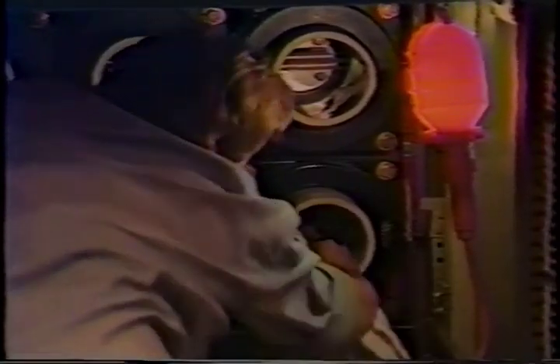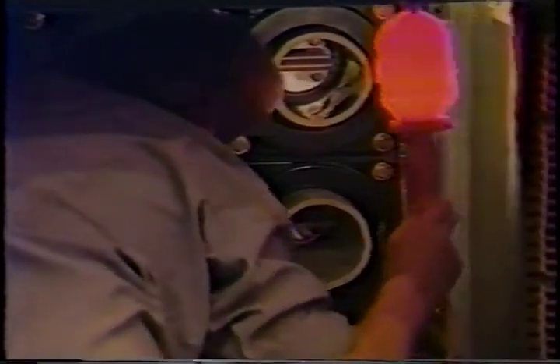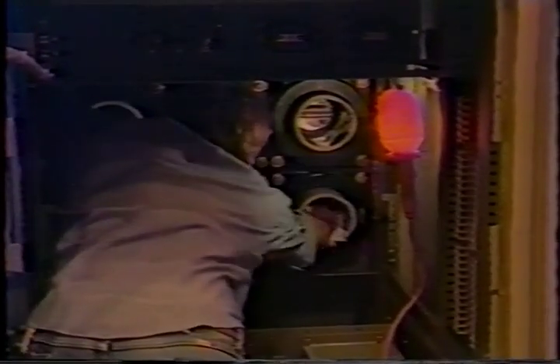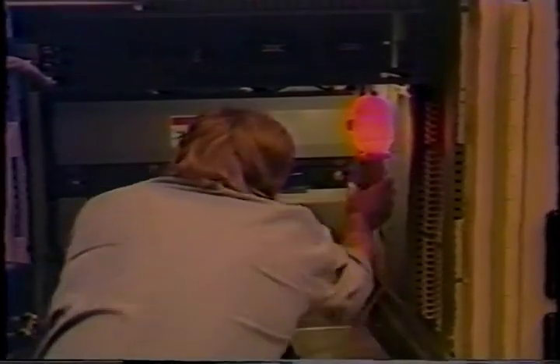For maintenance of disconnecting contacts and supports, remove each breaker from its compartment. De-energize primary circuits and expose primary contacts and their supports. Wipe clean with a cloth moistened in a non-flammable solvent. Inspect for abnormal wear or overheating. Discoloration of the surfaces is not harmful unless corrosion due to atmospheric conditions is severe, leaving deposits on the surface. If necessary, these can be removed by a light application of crocus cloth.